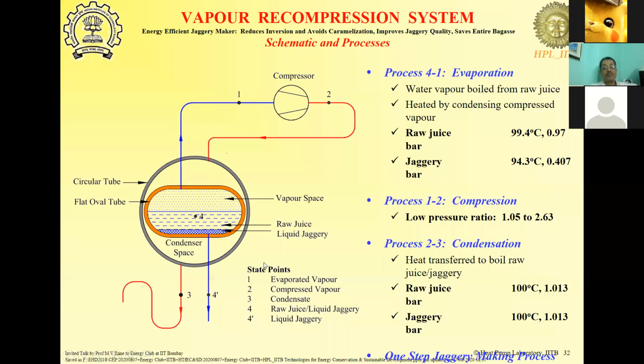If you look at it from the first law principle, whatever heat is required to boil gets added with the compressor power input, and then the total heat is supplied. So we always have extra heat available to boil than what is actually required. Even after accounting for heat losses and things like that, we still have sufficient heat to continue the process once it is initiated.